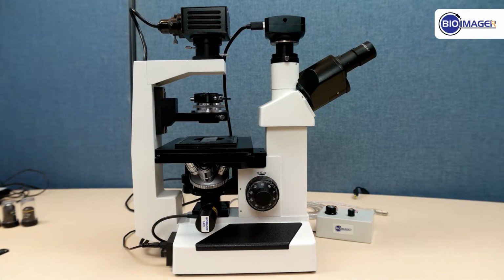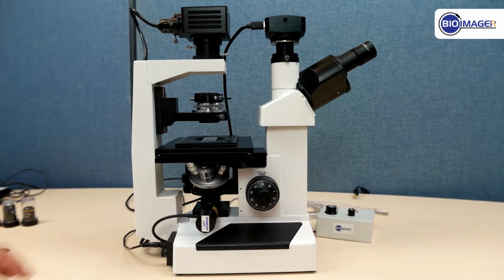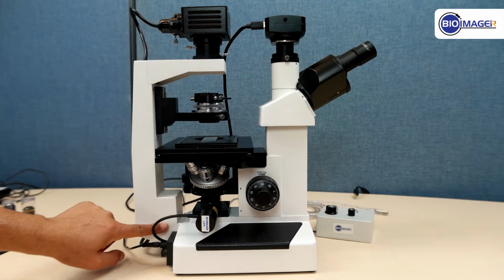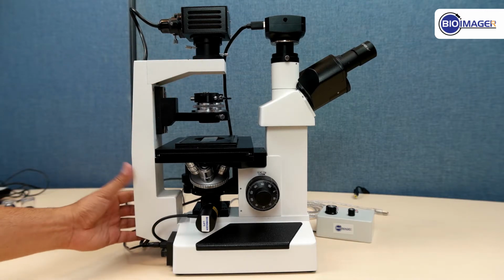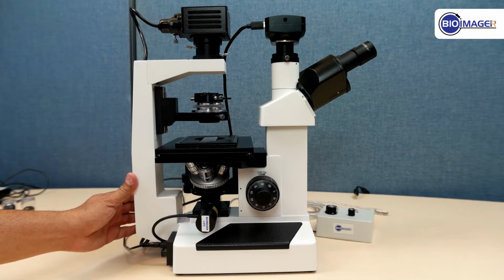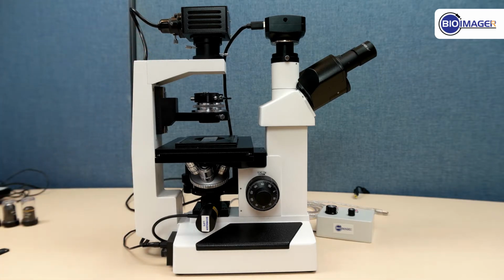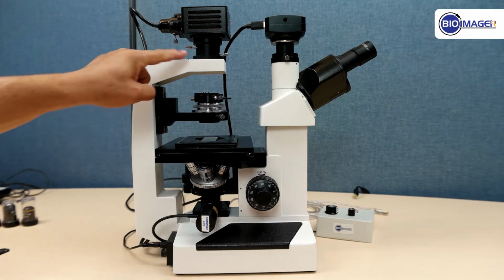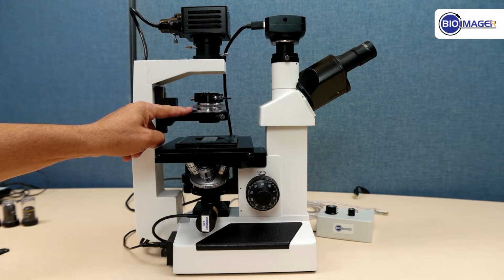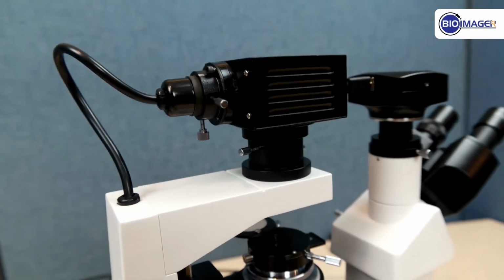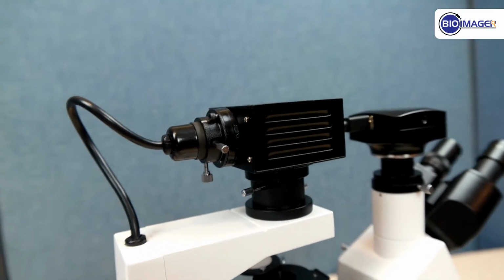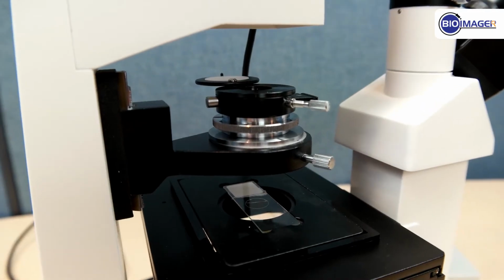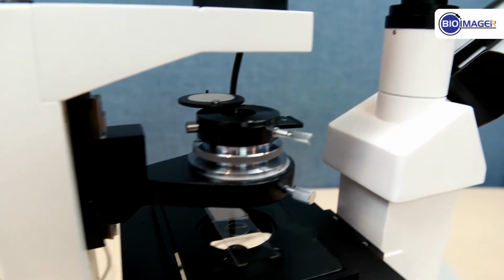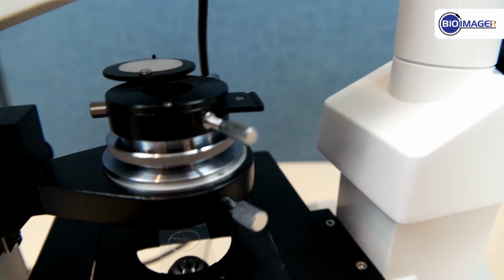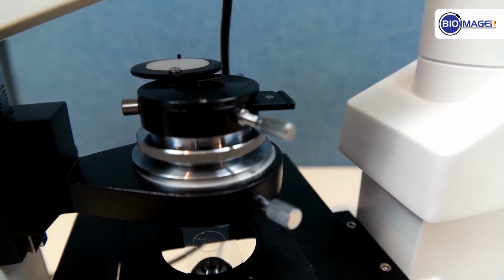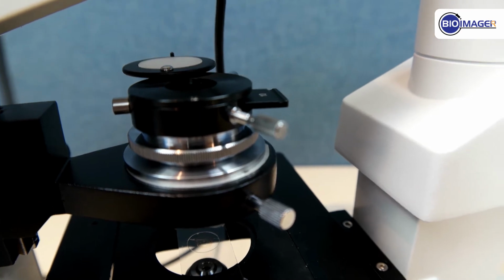The phase contrast in this microscope is super easy to use. It is mounted on this L-shape or C-shape module, which is detachable from the microscope. The illumination is designed based on Köhler. You have a field diaphragm at the top and an iris diaphragm at the center. You can adjust the location of the LED in X, Y, or Z directions, move the condenser up or down, and also select different phase annuli. The condenser working distance can be selected from 30 mm to 70 mm.